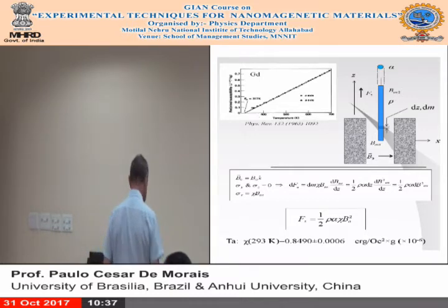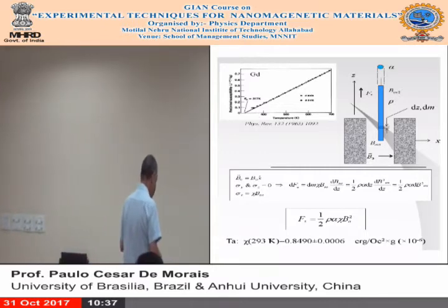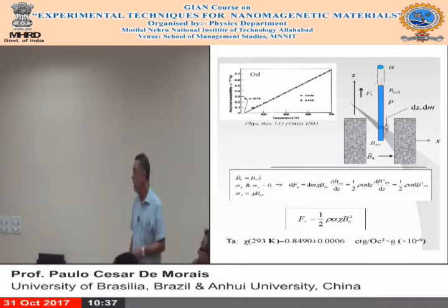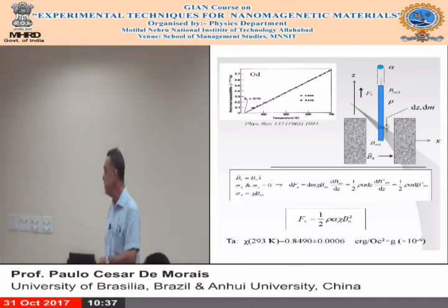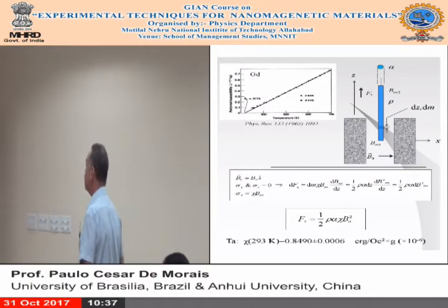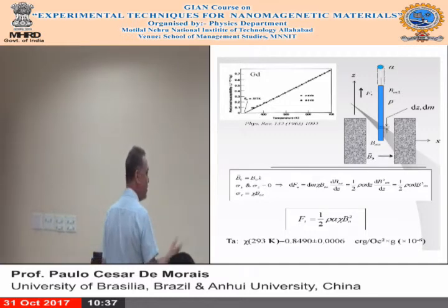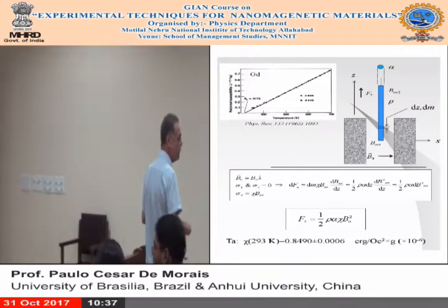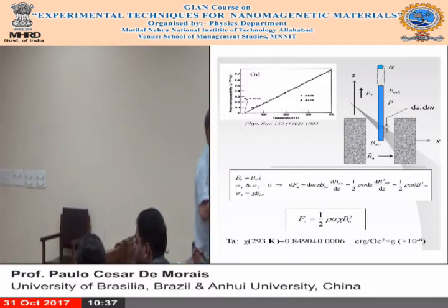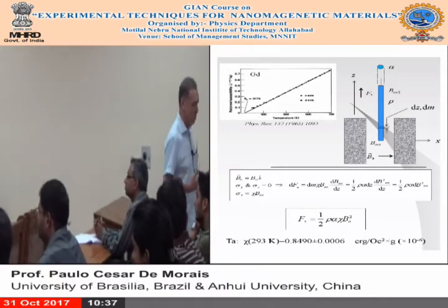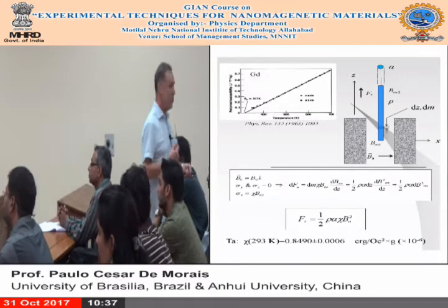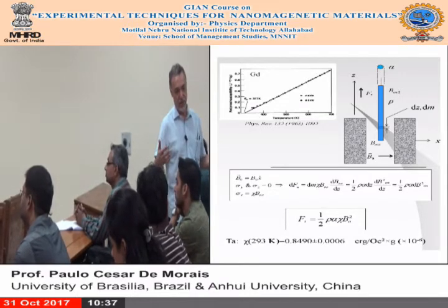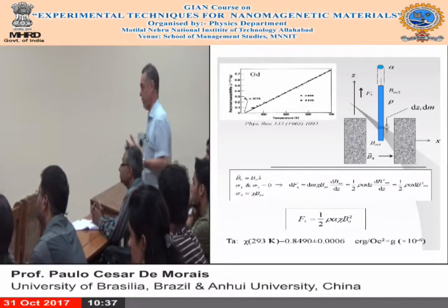So, of course, you need to calibrate. Calibration, usually, you can use, for instance, tantalum to calibrate the system is another calibration material. Besides nickel metal is too strong to calibrate susceptibility. It is good to calibrate magnetization, but it is too strong, actually.